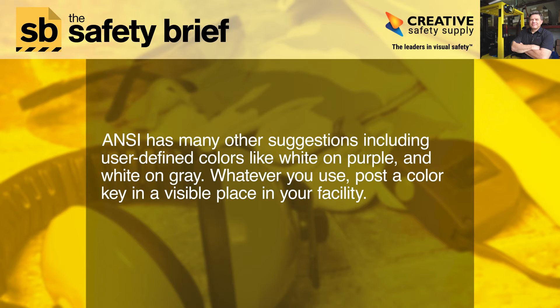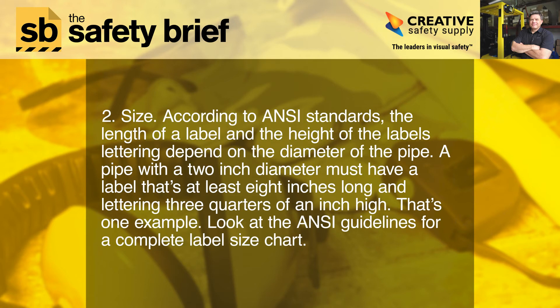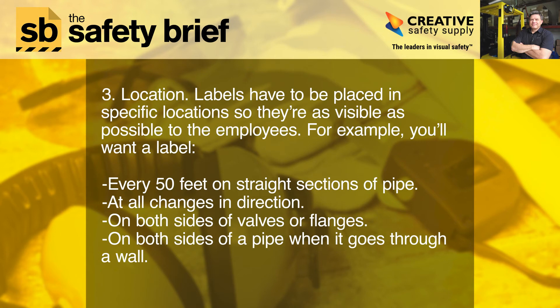Whatever colors you use, post a color key in a visible place in your facility. Two: size. According to ANSI standards, the length of a label and the height of a label's lettering depend on the diameter of the pipe. For example, a pipe with a two-inch diameter must have a label that's at least eight inches long with lettering three-quarters of an inch high. Look at the ANSI guidelines for a complete label size chart.